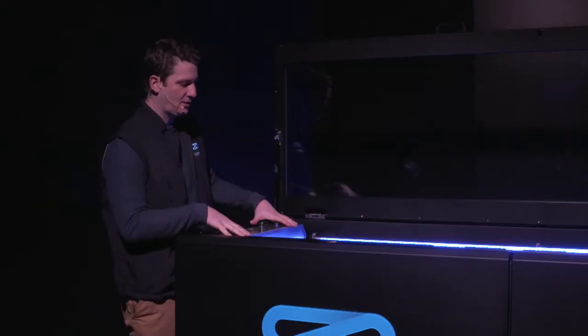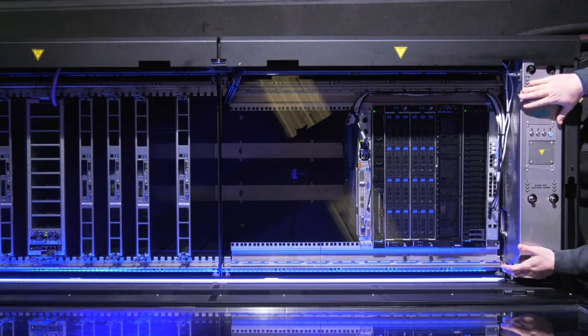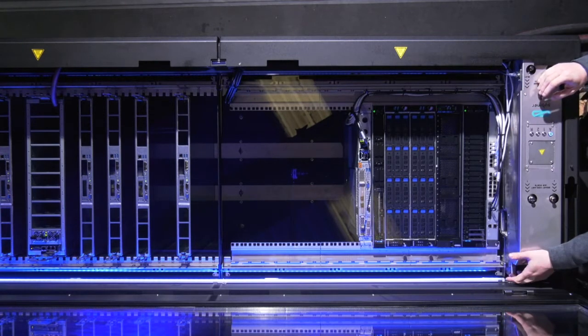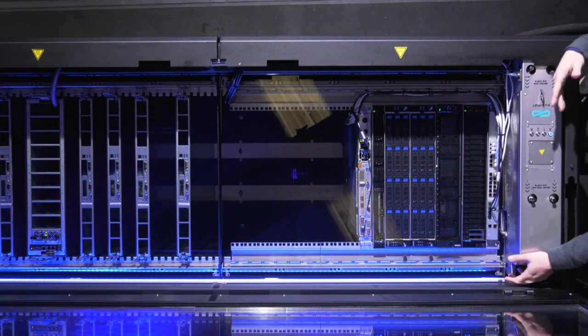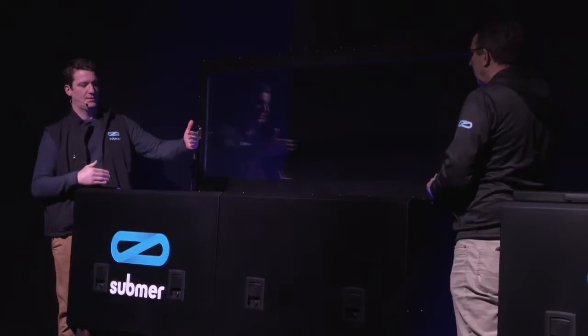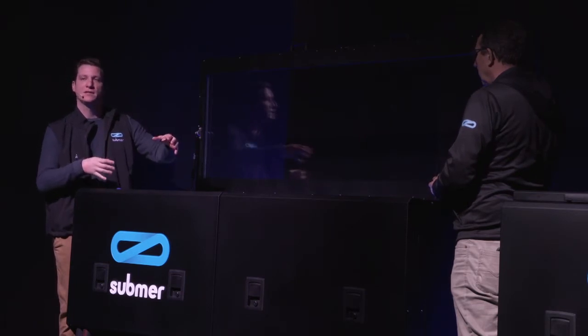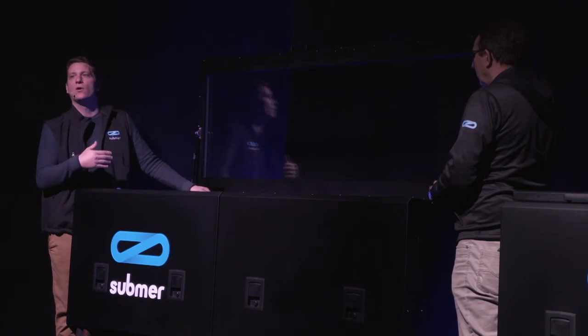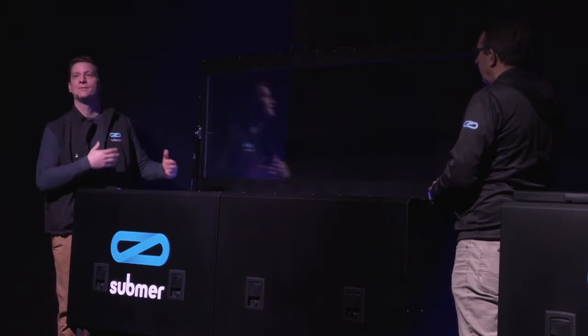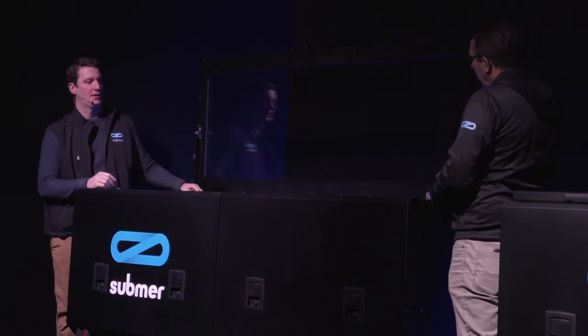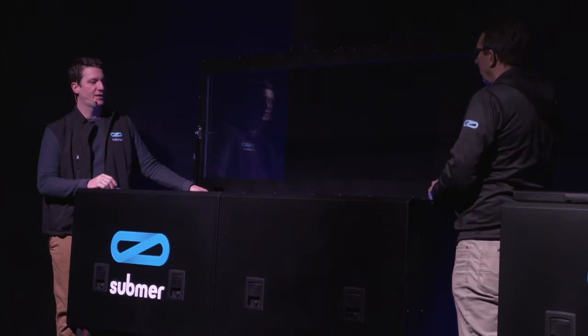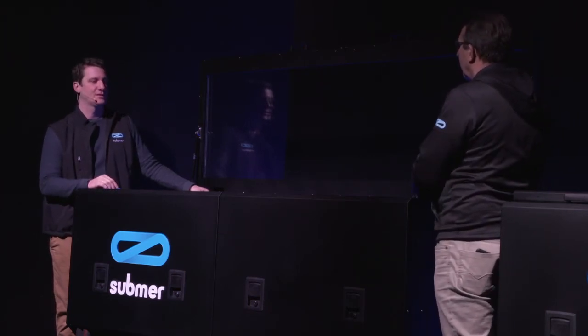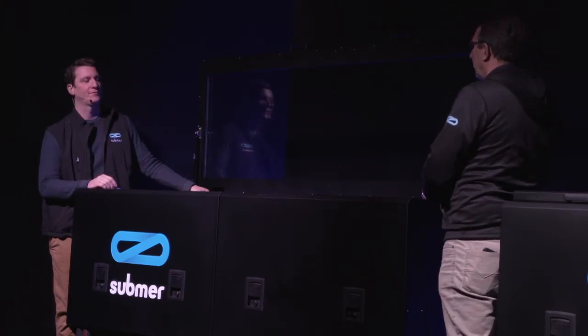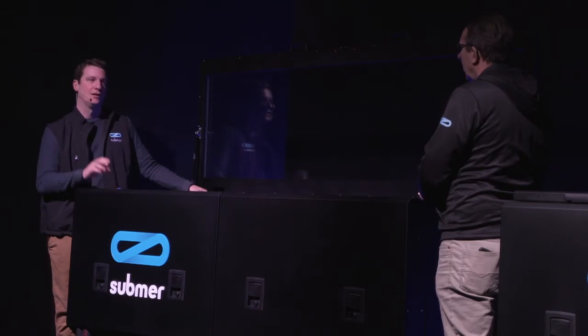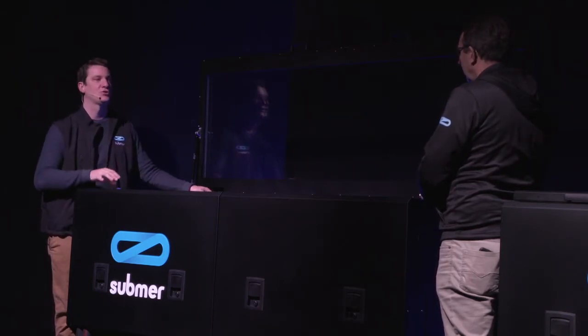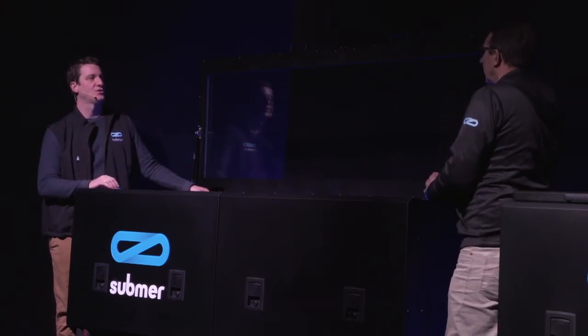So very briefly again about the CDU, the brains of the machine. In this unit we just have 1, which means we have 50 kilowatts of dissipation capability. We do have the possibility of deploying 2 CDUs in this system, which means we can either provide more redundancy and resiliency by bringing separate water feeds to each CDU, or we can completely add up the dissipation capability of each of those CDUs as well. And that means that we can go up to a tier 3 deployment. Tier 4, and actually we're very close. We're working with the Uptime Institute to get an official certification from them regarding that, because a lot of our customers are asking us, I want to make sure that this cooling system is not going to disrupt my tier certification with the Uptime Institute.